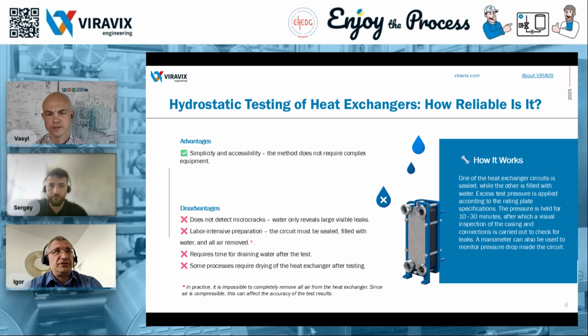This makes it especially attractive for facilities aiming to keep testing simple and fast. However, a key limitation of the hydraulic test is that it only detects obvious leaks when problems are already present. In other words, it can't predict or warn in advance that a critical leak is about to happen. Another significant drawback is that the pressure must be raised to the maximum level permitted by the manufacturer, which can create additional stress on the unit and increase the risk of causing damage during the test itself, especially if the equipment is already worn or aged. Well, to make the test meaningful, the pressure must be high enough. The lower the pressure, the lower the chance of detecting a leak.